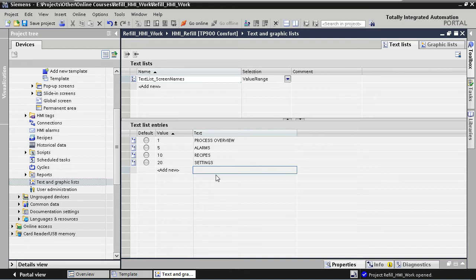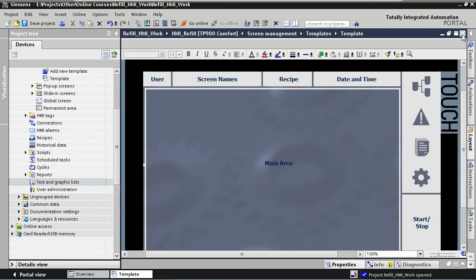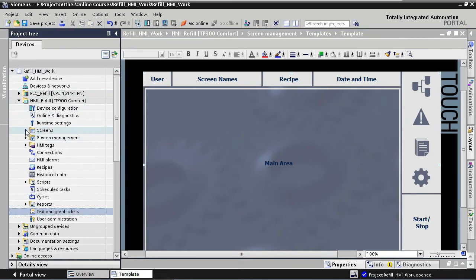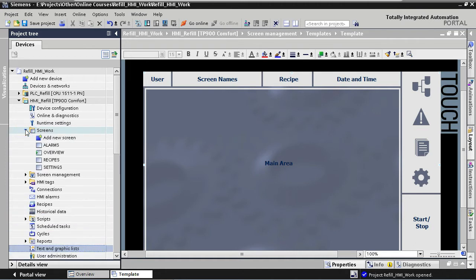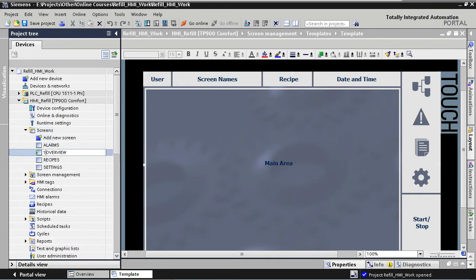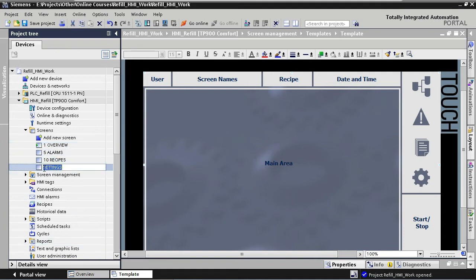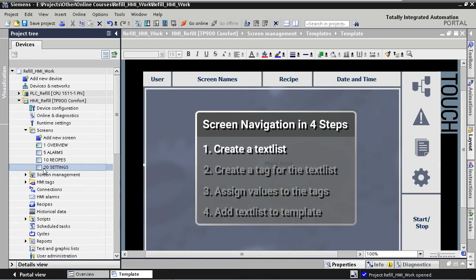So by creating some distance between the values of the main screens, you allocate some space for more possible screen additions in the future. Now, I would like my screen names to include the screen value. The reason for this is that it will straight away be clear which screen has which value, and furthermore it will automatically order the screens by number under the screen group. So for each screen name, I add the screen number to the front of the name. That's it for step 1.